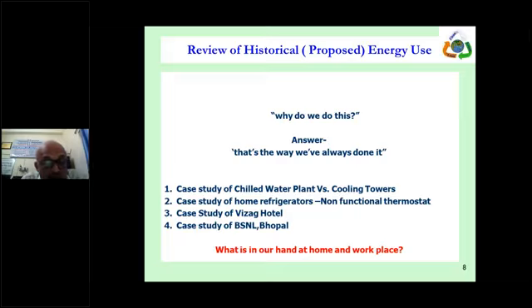So there was no proper check of how much TR was actually required, and how much each system was supplying. Then we did the overall heat load calculation for the whole building, and came to know the total TR required, and how much TR was actually put in operation. There was a huge gap. Then we suggested that you stop using the DX system, and for the AHU connected with DX, replace that coil, putting a chilled water coil instead of the DX coil, and there was scope in the chilled water plant for applying more chilled water.